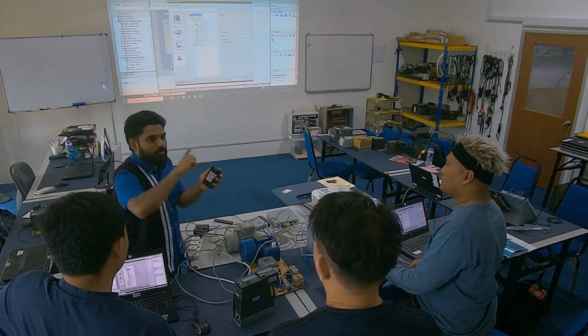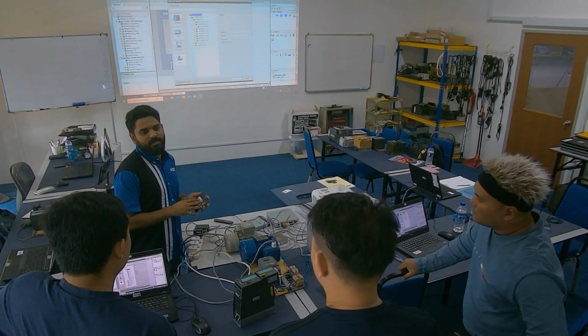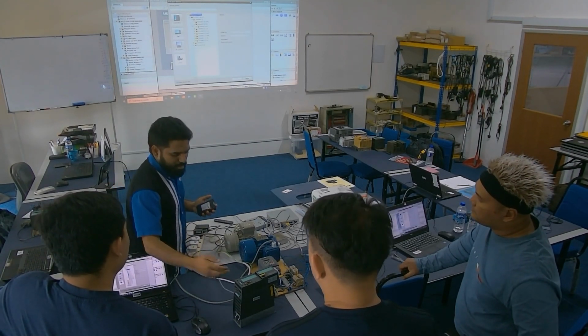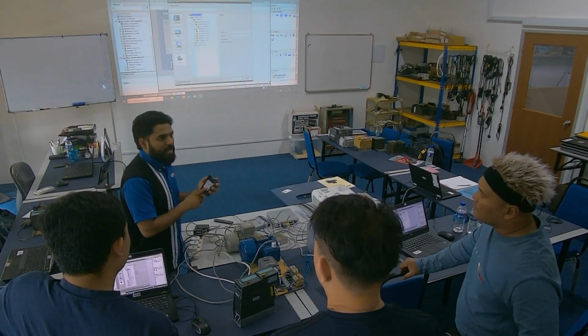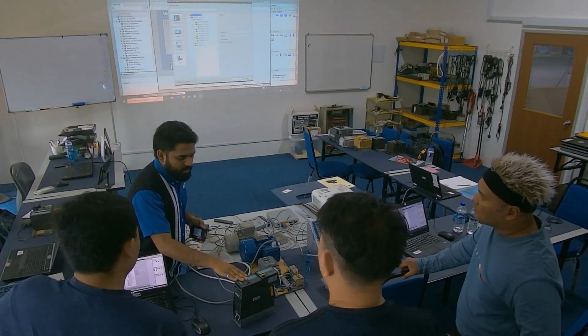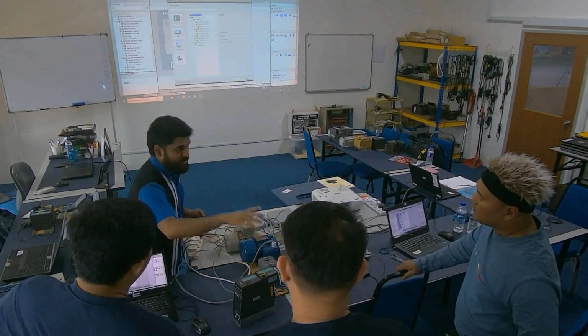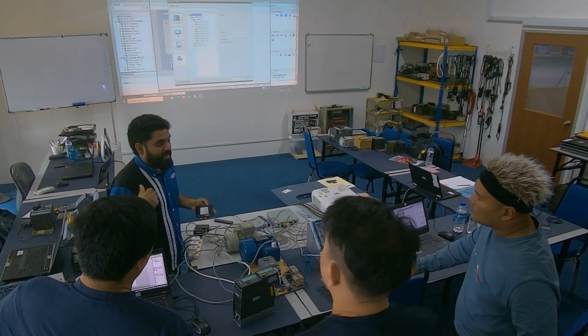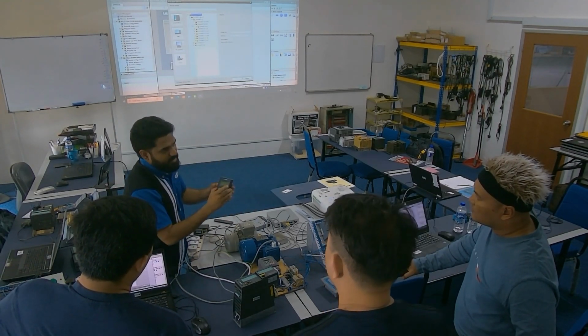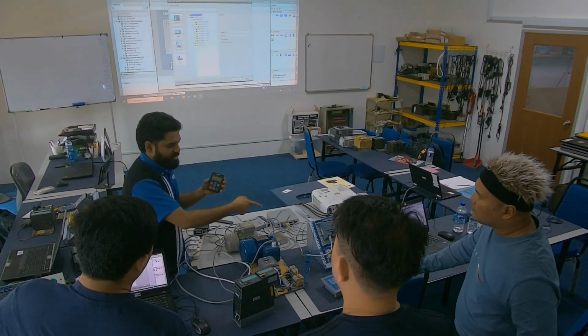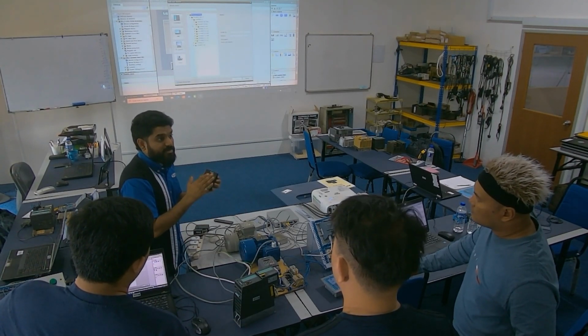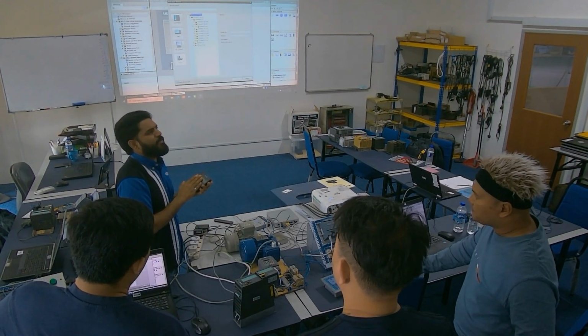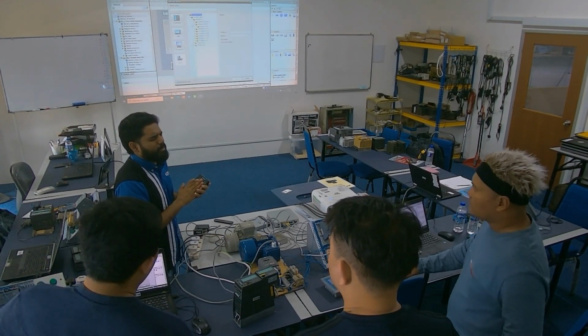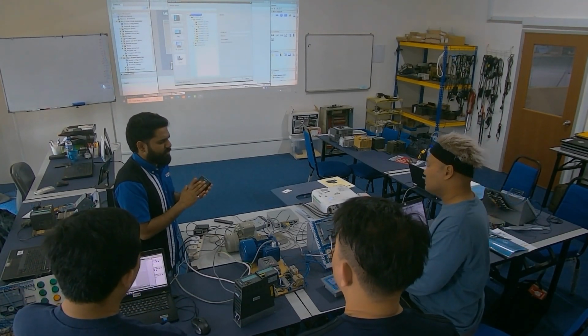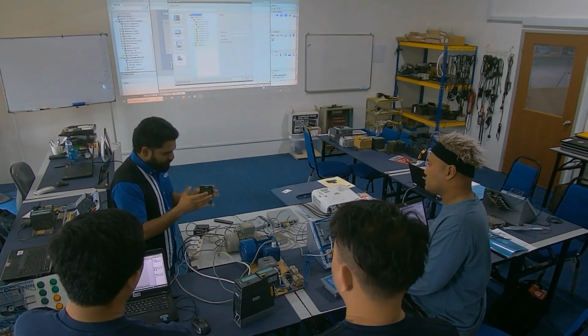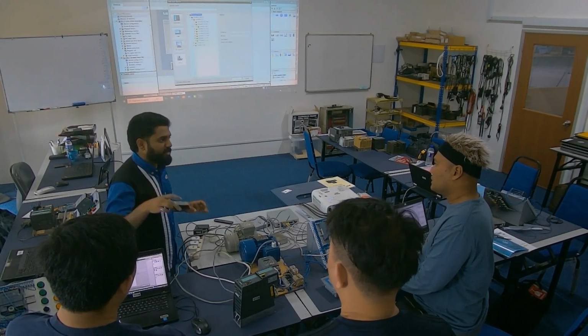Then from here to another VFD also. So this is normally what they put in a machine company — they have let's say 10 drives but only one panel. So what they do, let's say this one really breaks down, what happens? Let's say you have a spare, you go to the next VFD, connect this, copy, backup, same like just now with the HMI — backup and restore. Backup to here, they have backup to ROM, EEPROM or something, read-only memory. So you backup to here, then you connect to the other drive, you can restore it.